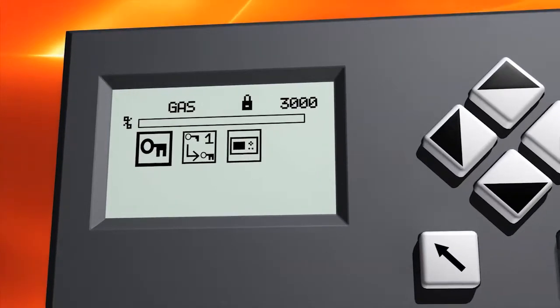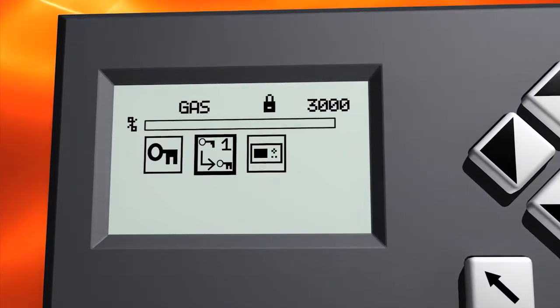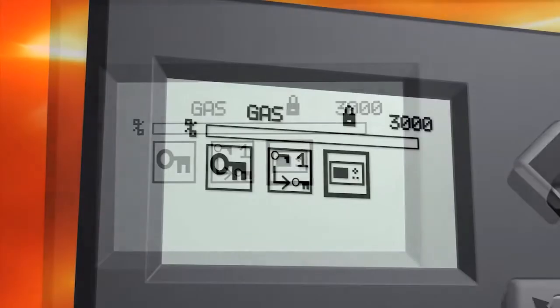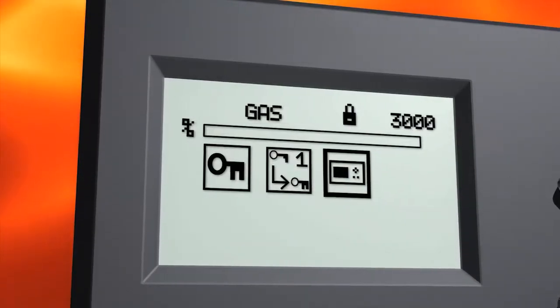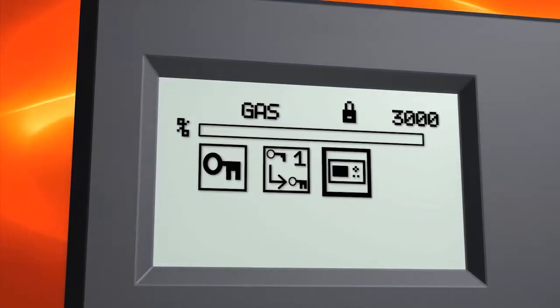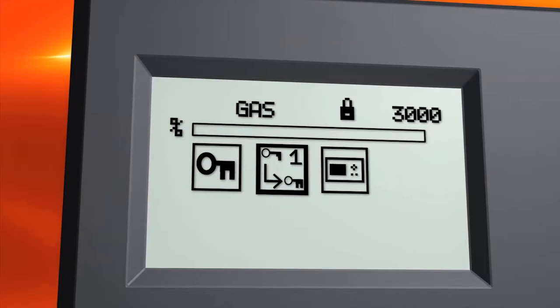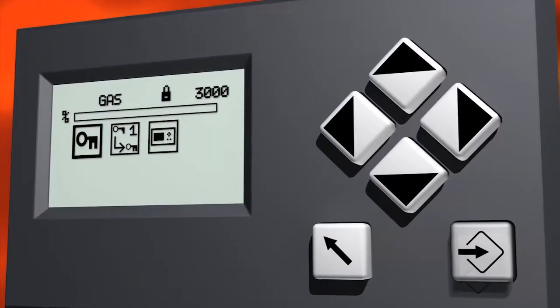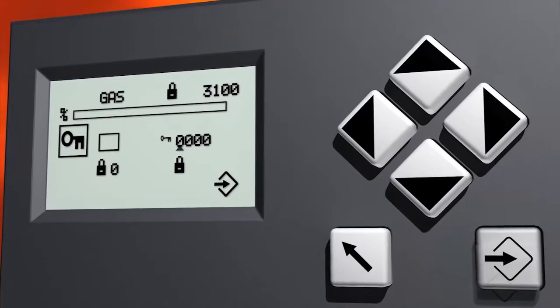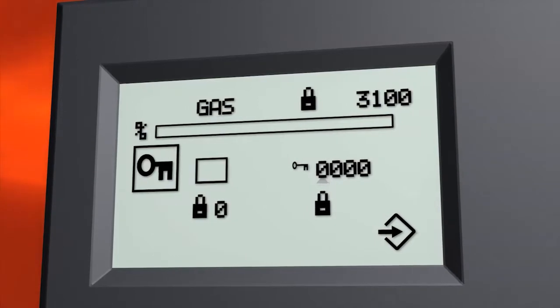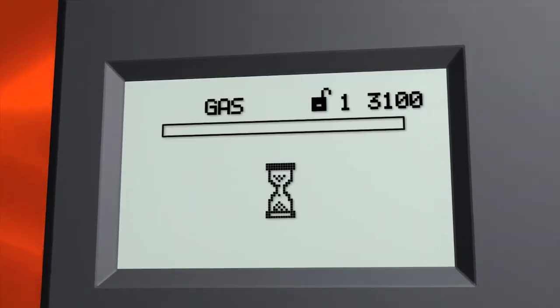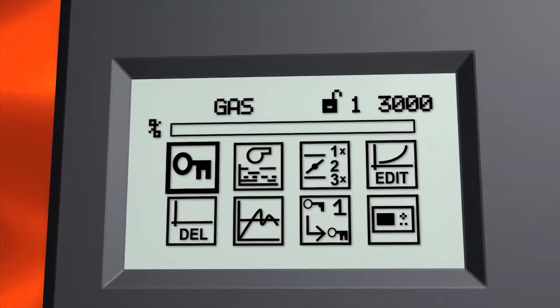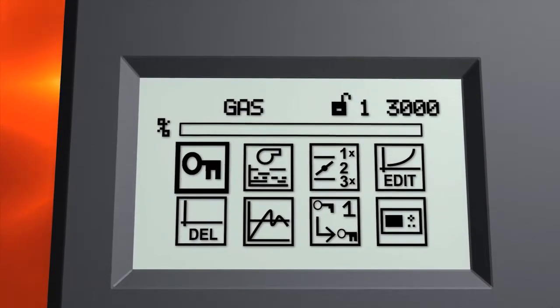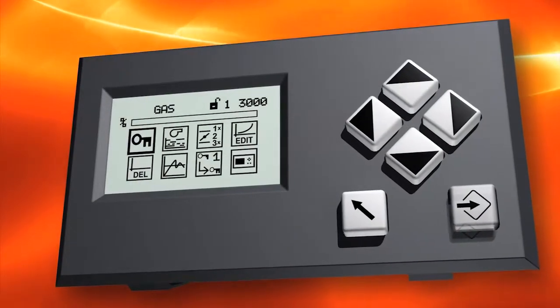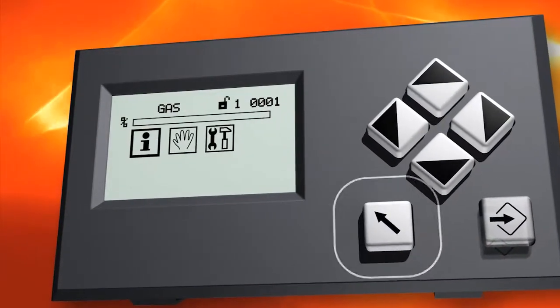On this menu level you can see a key symbol, a password change icon, and a menu for the operation panel, where you can change screen brightness and other settings. First, you should log in with a password. Highlight the key icon and press Enter. You can type in the password using the arrow keys. On the first operation level, you can only monitor the burner operation. Entering the next level with a password enables you to commission the burner and change settings. After setting the password, press the back button to return to the previous menu.